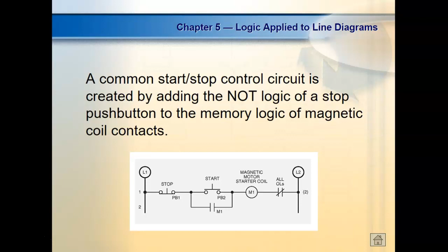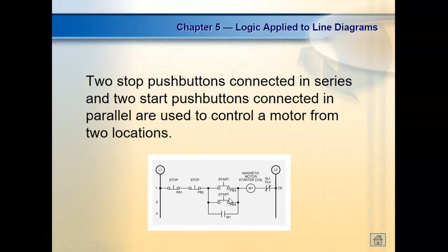In this particular one, they've got two stop push buttons as well as two start push buttons, so they've set up AND logic and OR logic together to create the circuit. Again, this goes back to having two control panels. Either control panel will start my motor running, and this is how I'd set up that circuit using memory as well as AND and OR logic.